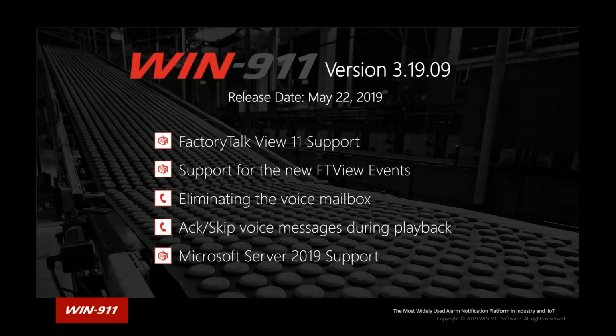I think the big thing is we will have support for FactoryTalk View 11 on this next release. The big change, I think, in FactoryTalk View 11 is this idea of FactoryTalk events. We've always been filtering and monitoring all the alarms that come through with FactoryTalk, but now this event is also coming through. We had to make a slight change here because an event doesn't have an acknowledgement property. Part of its property levels, there's no acknowledgement for it.